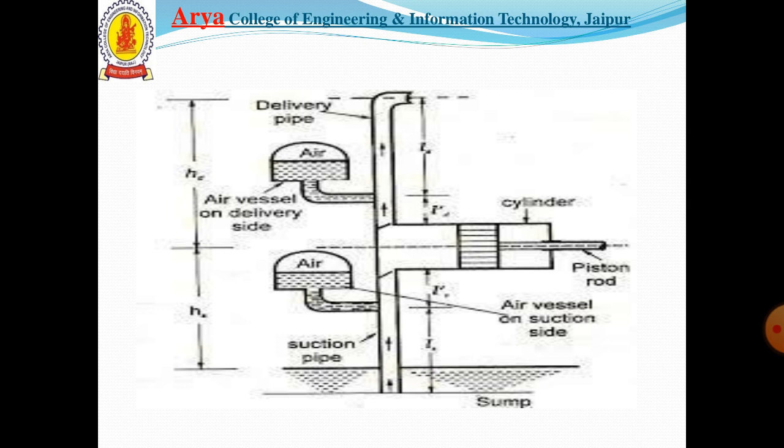When the liquid level in the air vessel rises, the air above is compressed, and this compressed air forces the liquid out as soon as the pressure in the pipe falls. The variation in air pressure may be reduced by increasing the capacity of the air vessels. The liquid in the delivery pipe beyond the air vessel is assumed to flow with a uniform velocity vd.